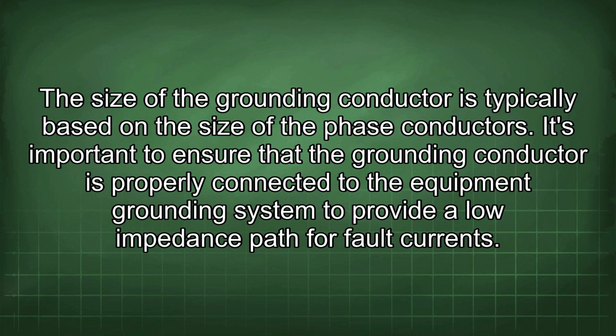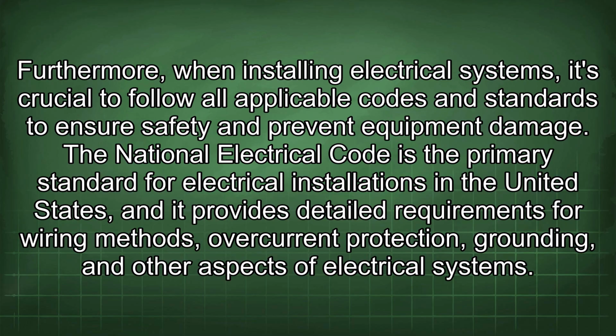The size of the grounding conductor is typically based on the size of the phase conductors. It's important to ensure that the grounding conductor is properly connected to the equipment grounding system to provide a low impedance path for fault currents. Furthermore, when installing electrical systems, it's crucial to follow all applicable codes and standards to ensure safety and prevent equipment damage. The National Electrical Code is the primary standard for electrical installations in the United States, and it provides detailed requirements for wiring methods, overcurrent protection, grounding, and other aspects of electrical systems.